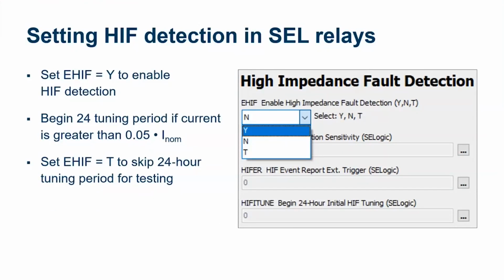Let's start off with some of the settings here. Of course, we have an enable. You'll notice we have three options here. It comes default set to no, if this is available in the relay, and it will be disabled. We can set enable for EHIF to yes, Y, and that will enable high impedance fault detection, or we could set this to T.